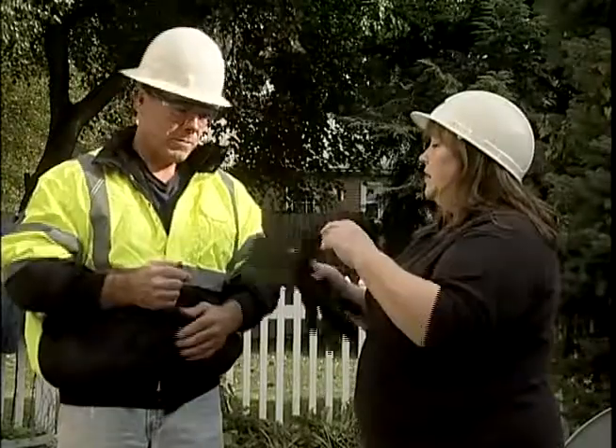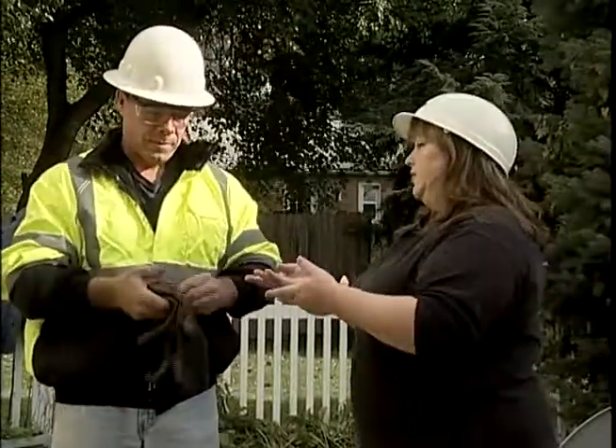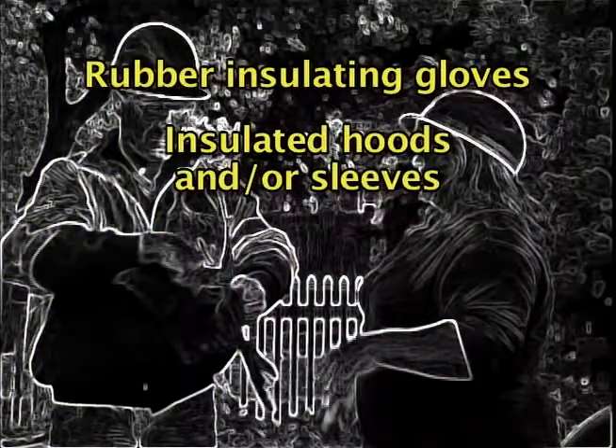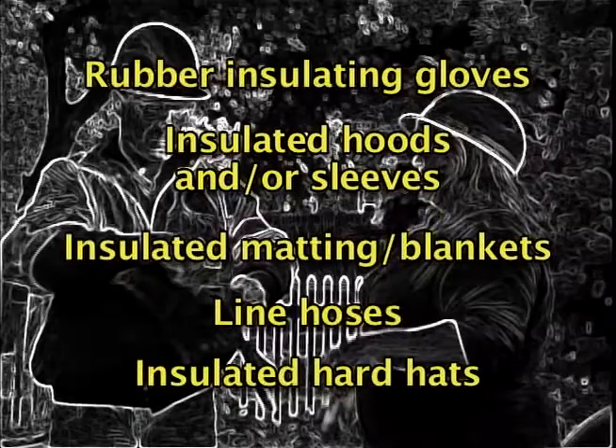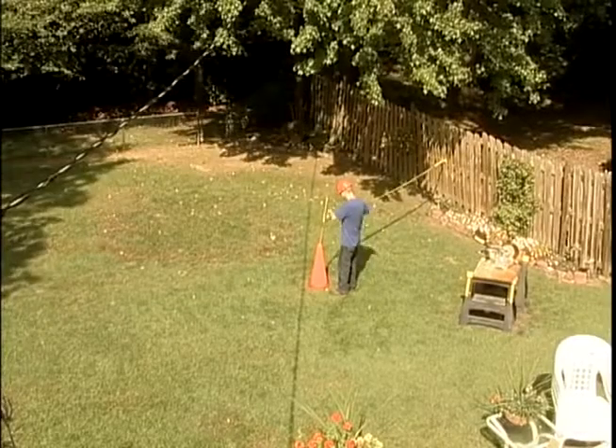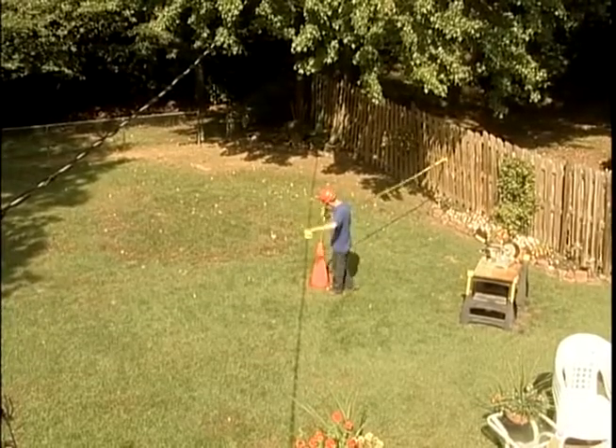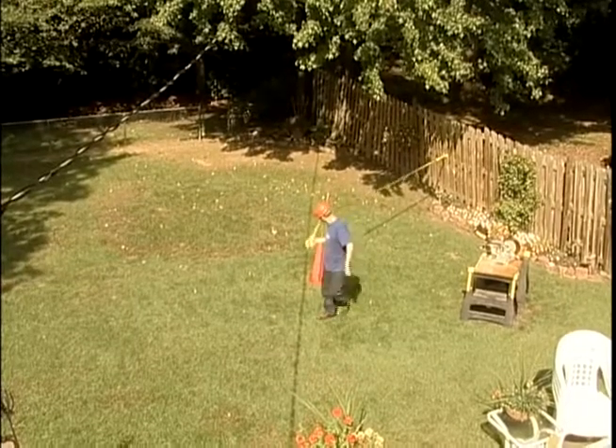from the lines and that they use protective equipment and tools, such as rubber insulating gloves, insulated hoods and/or sleeves, matting or blankets, line hoses, insulated hard hats. Other protective measures such as guarding the power lines or installing insulated sleeves can also be used.